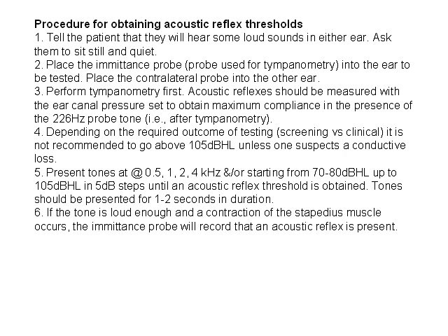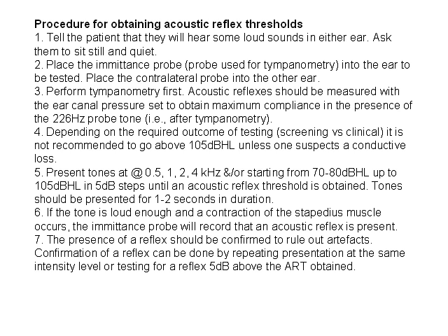If the tone is loud enough and a contraction of the stapedial muscle occurs, the immittance probe will record that an acoustic reflex is present. The presence of a reflex should be confirmed to rule out artifacts. Confirmation of a reflex can be done by repeating presentation at the same intensity levels or testing for a reflex 5 dB above the acoustic reflex threshold obtained.